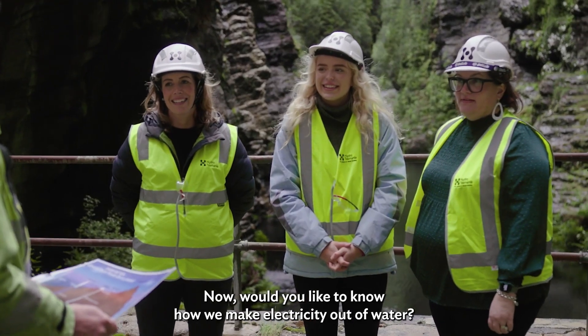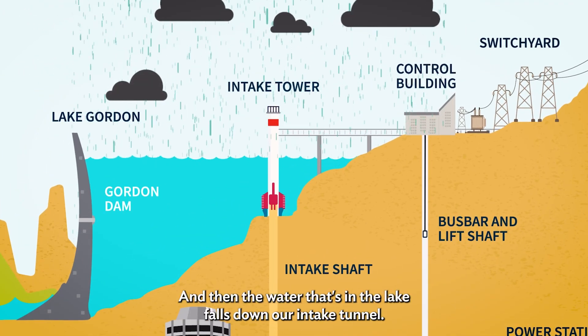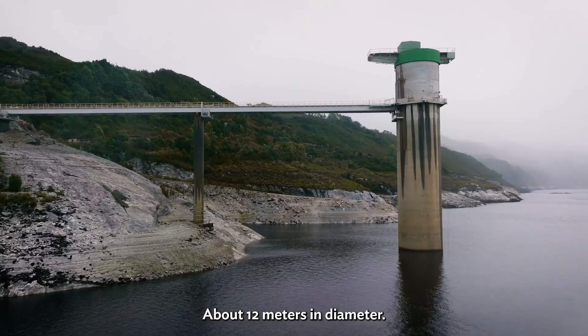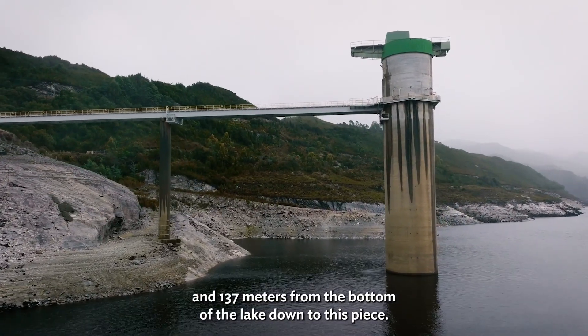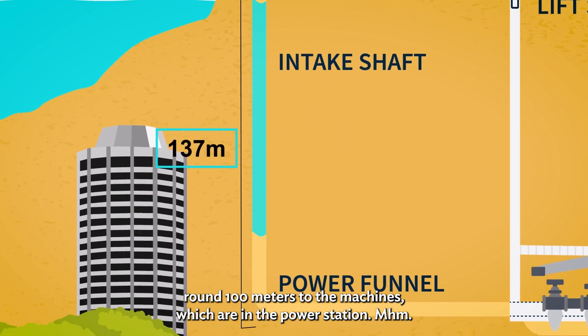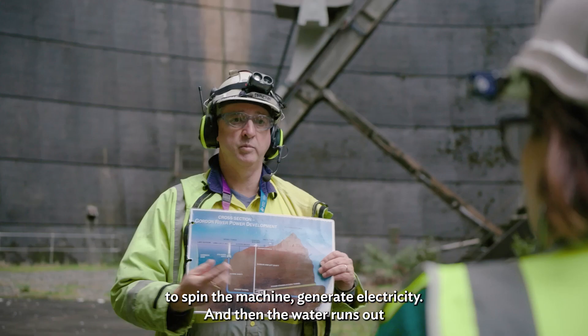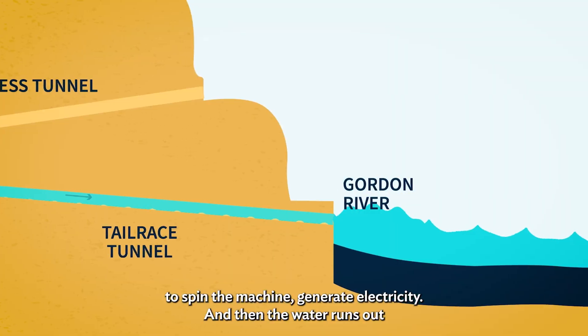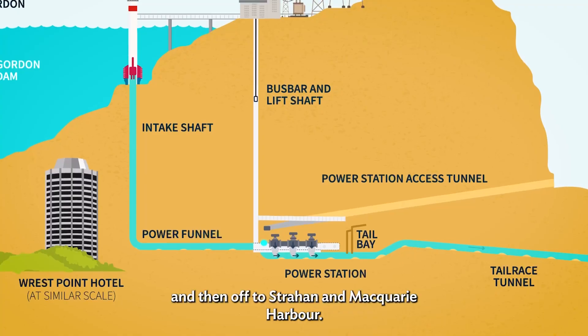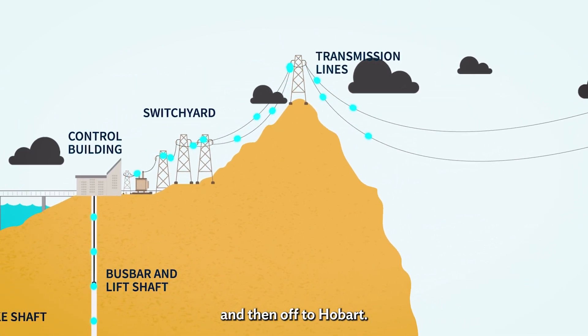Would you like to know how we make electricity out of water? We have the big Gordon Dam. The lake fills up from lots of rain, and then the water in the lake falls down our intake tunnel, which is about 12 metres in diameter and 137 metres from the bottom of the lake down. Water then runs around 100 metres to the machines in the power station. Each machine needs 90,000 litres of water per second to spin the machine, generate electricity, and then the water runs out what we call the tail race tunnel back to the Gordon River — and then off to Strahan, Macquarie Harbour. The electricity generated comes up the lift shaft through big conductors and off to Hobart.